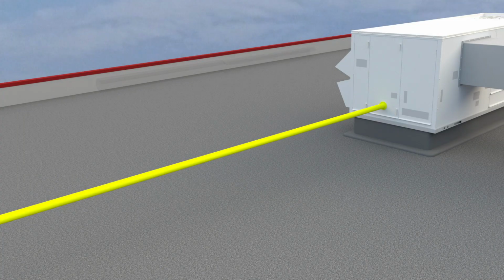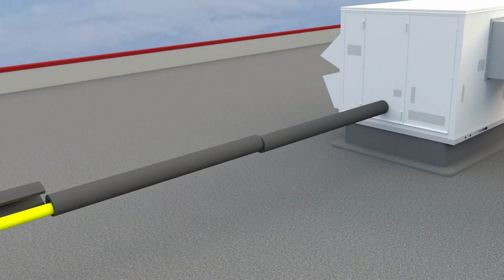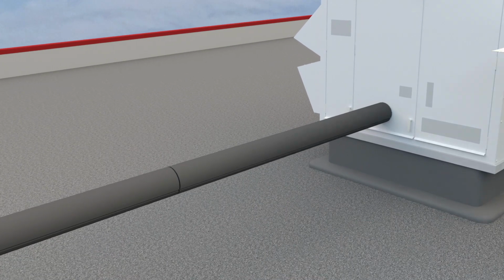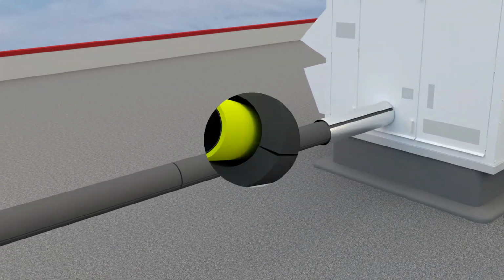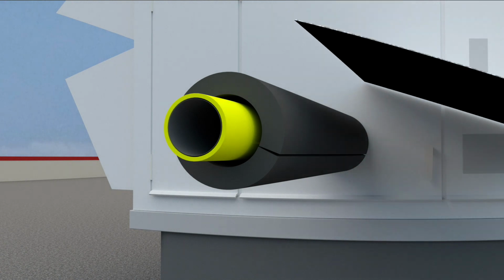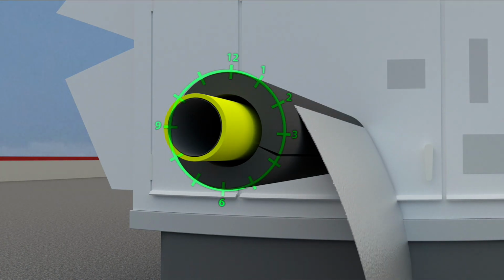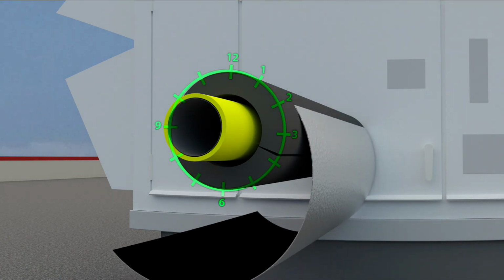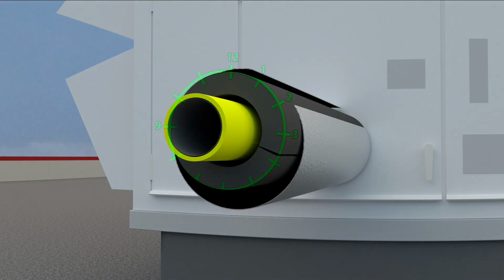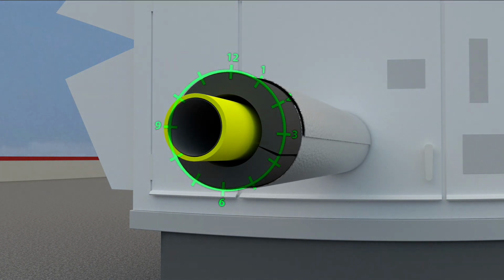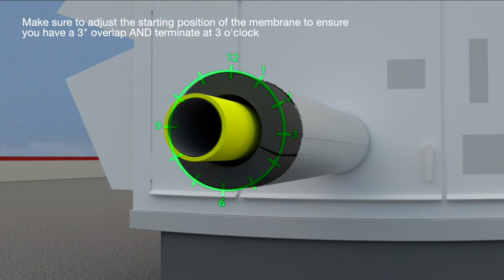For piping applications, install the insulation such as Armaflex per the manufacturer's recommendation. This is a key point. Start installing FlexClad at roughly the 2 o'clock position. Wrap the membrane clockwise around the pipe and terminate at 3 o'clock. Make sure that there is a 3-inch overlap, so you may need to adjust the starting position of the membrane in order to ensure a 3-inch overlap and terminate at 3 o'clock.